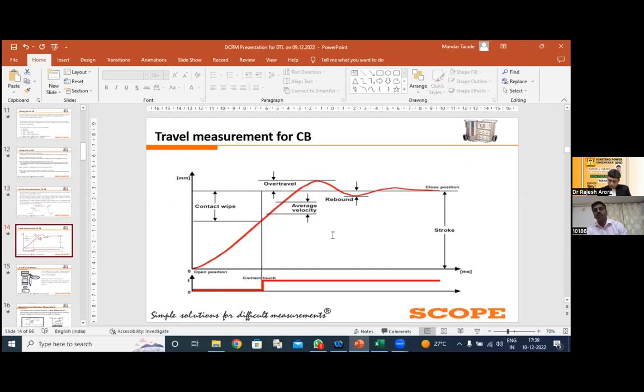Next, the travel measurement for the CB. This is very important. In my consecutive slides, you will get a better idea about the travel measurement, because with its help we can comment on different parameters like the total travel, the contact wipe, the contact gap, the rebounds, the over travel, or the arcing contact tip length. These are some of the parameters we can identify with the help of the travel measurement of the CB. Here, the travel measurement is nothing but the indication of the instantaneous position of the CB during operation.